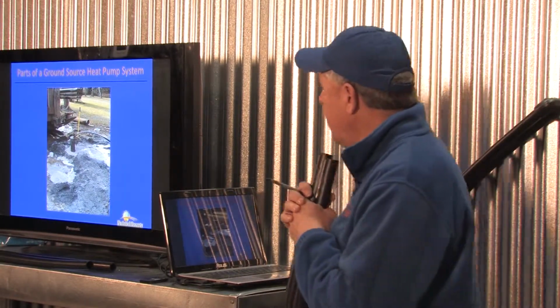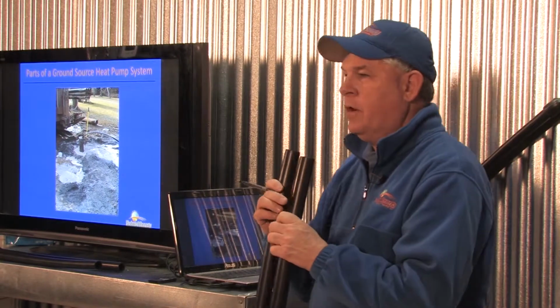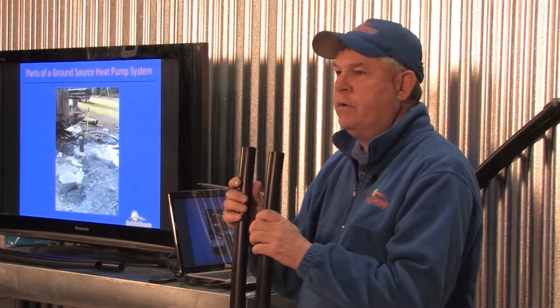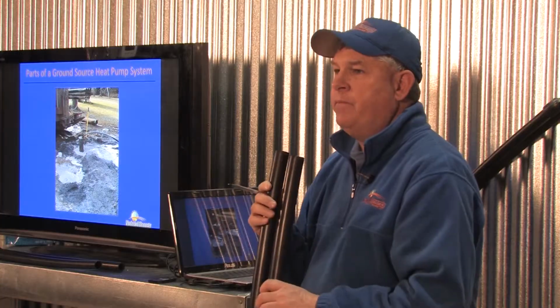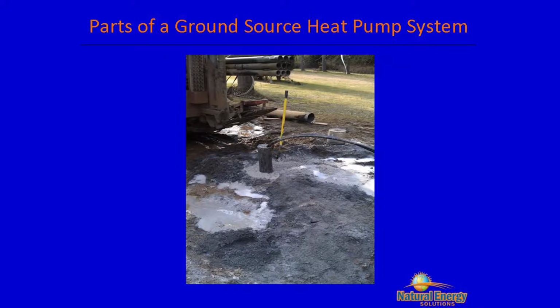Okay? However, when this hole is drilled, not a well, when this borehole is drilled, we insert this pipe, we now seal that hole shut. You see, there's no hole. It's clay, bentonite clay, called grout. We grout this hole shut. That keeps this pipe in thermal contact with the earth, gets a great energy transfer, but it also has an environmental benefit of sealing all the aquifers off, sealing this hole off so we can't have any kind of contamination.